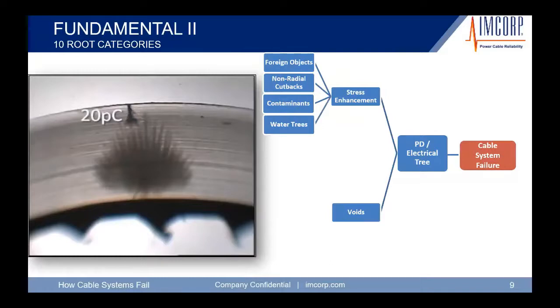Water trees. So, of course, we always hear that water trees are going to cause cables to fail. We always say, and we've documented, that in combination with a void, the stress enhancement areas will create these and will cause cables to go to failure. But mainly when there's a carbon tree that's associated with it. Now, there has to be some sort of defect, a manufacturer's defect or an installation defect, to bring the water to the particular area and then help grow that carbon tree to make that cable go to failure.